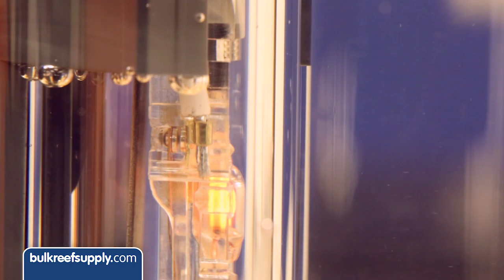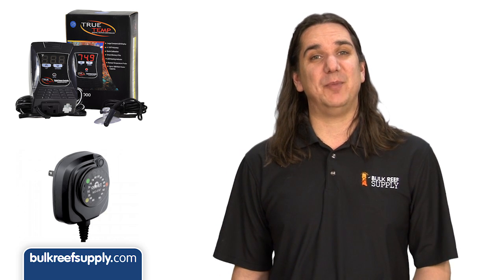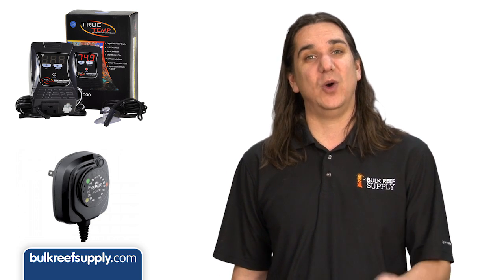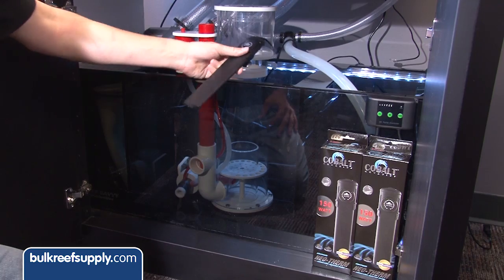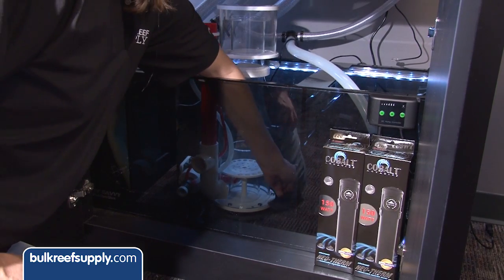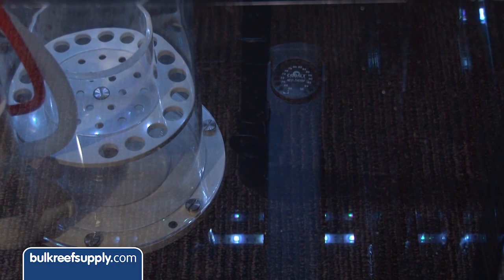Some of the more popular types are basically a 10-cent single point of contact. Some will fail off, and worse, some will fail on. Either way, it's bad news. The only real solution is an external temperature controller to add redundancy as well as alert you when a heater fails. Since heaters are often hidden down in our sumps, it's really easy to not know when something goes wrong, so the alarm is pretty critical.